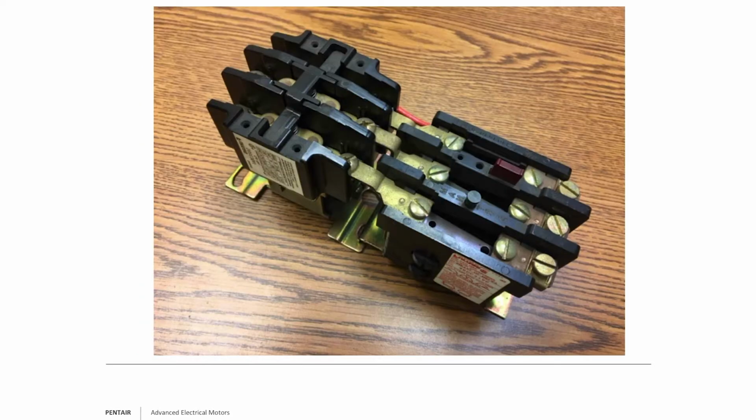When you're looking at these units for testing, if you test the incoming point to the exterior point when the unit is off and the mag relay is not energized, you should see OL or open. You should see the needle on the analog stay all the way to the left. You shouldn't see it moving because you don't want it passing voltage at this time. Then you can often push down on the center there, make the points contact. Again, of course, this will be with power off. Anytime you're testing with an ohm meter, make sure the power is off. So when you push down, then you should see 0, or ideally the analog meter should run to the right. This is at R times 1, and you want to see basically 0 or very close to 0. So when you push that button, that's where you want to make contact, and you're mimicking it passing voltage.